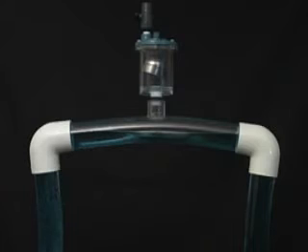If we close the shutoff valve mounted on the air release valve outlet, the orifice is no longer able to vent air. As a result, air collects at the high point and creates a restriction. This demonstrates the effects of air on system flow when air release valves aren't used.